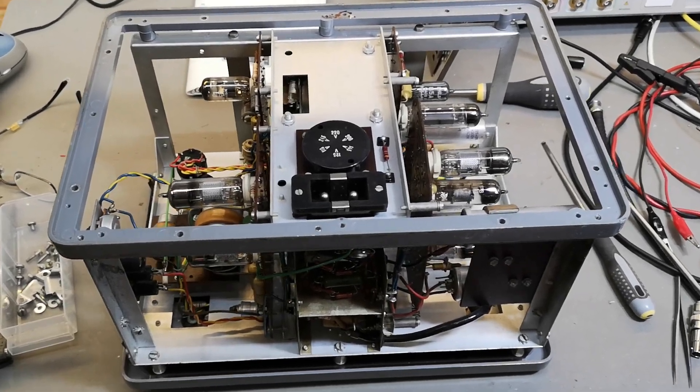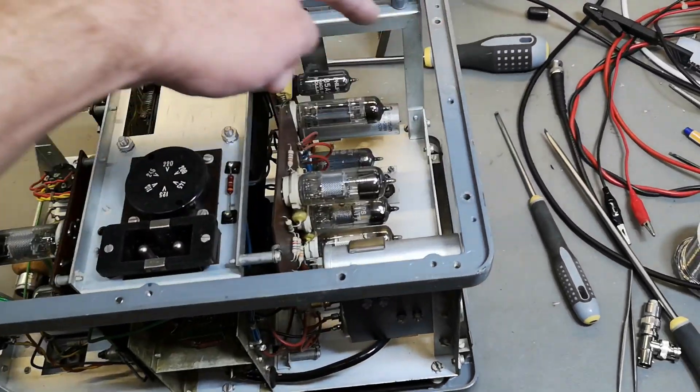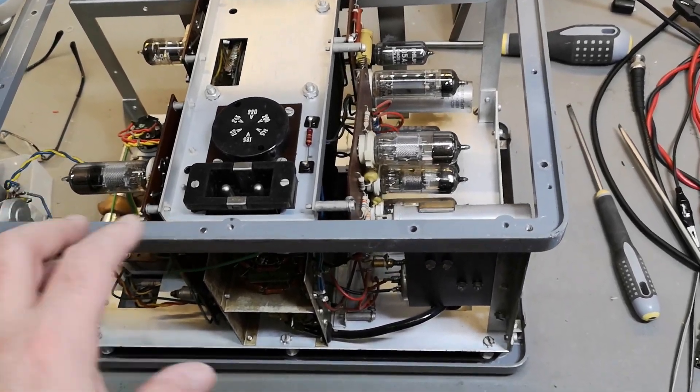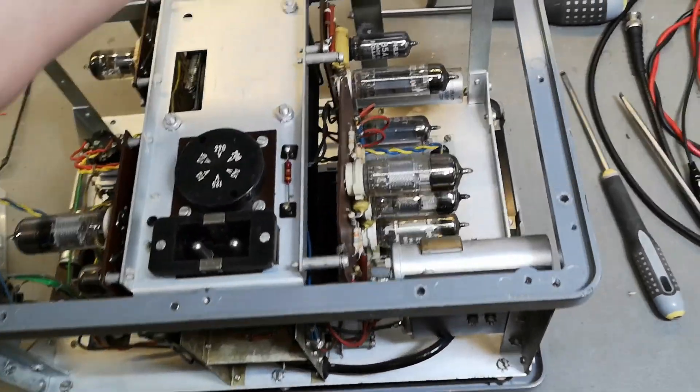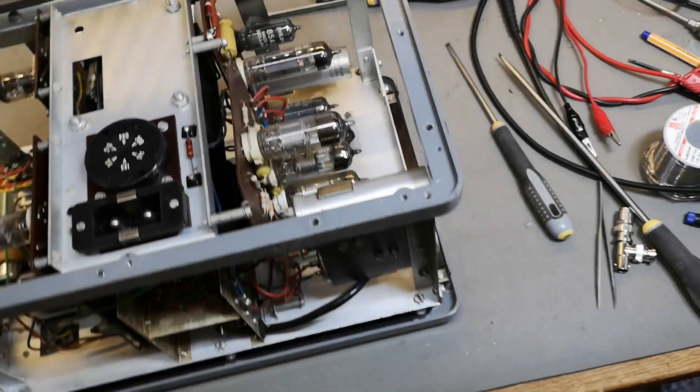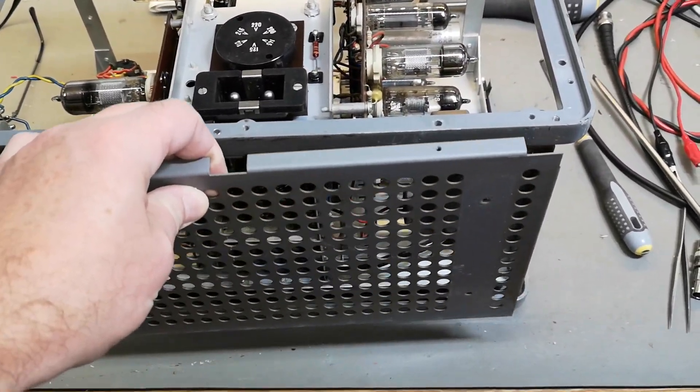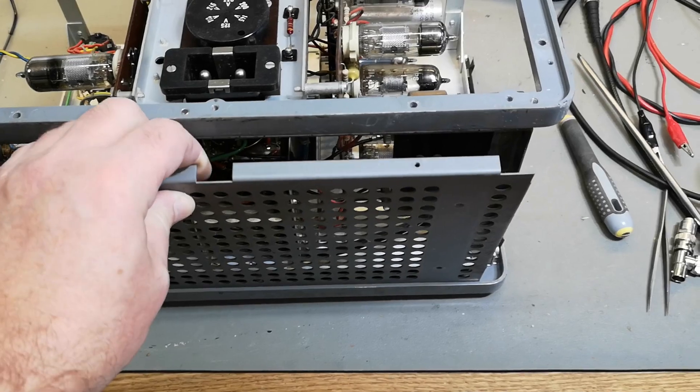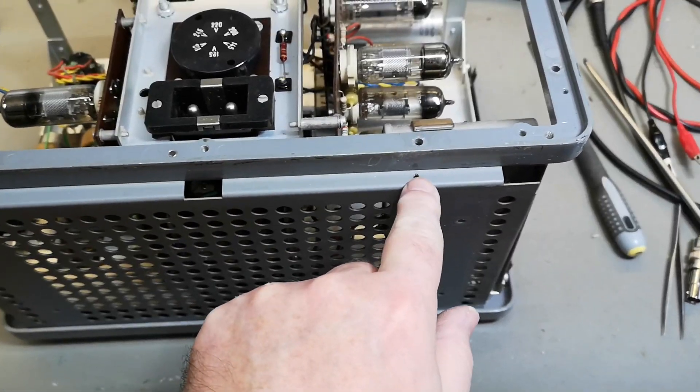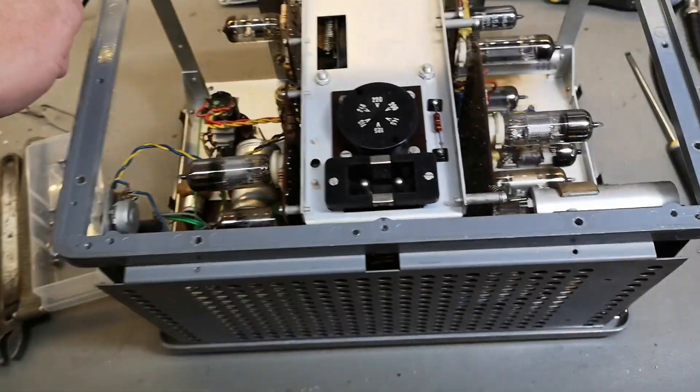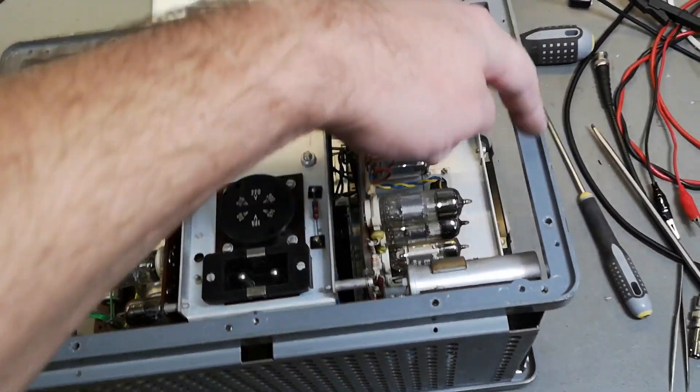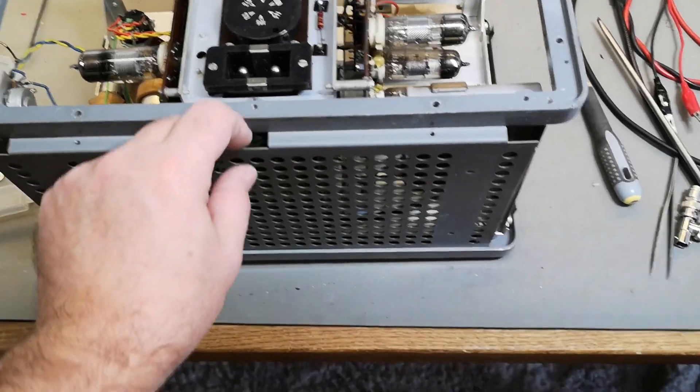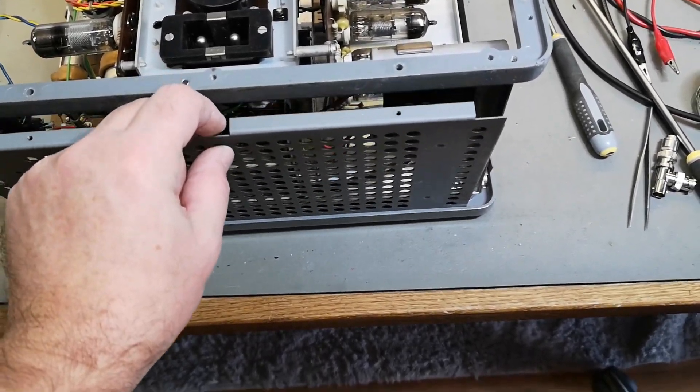So now I've removed all the side panels, so I got plenty of access all the way around this unit. There is a little secret trick to removal of all side panels. So of course you remove the screws here from the back to all the different panels, but then it can't get out.